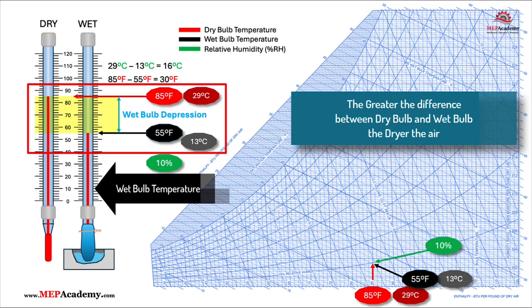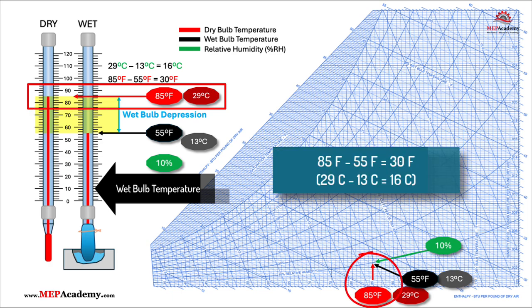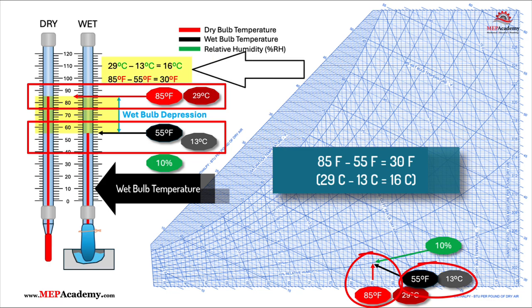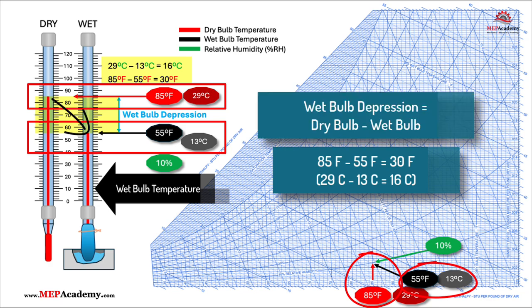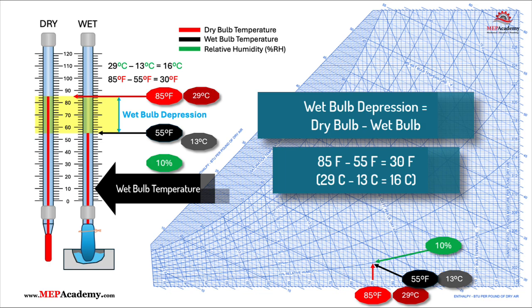We can see on this psychrometric chart that a dry bulb temperature of 85°F minus a wet bulb temperature of 55°F equals a wet bulb depression of 30°F, or 16°C. Wet bulb depression equals dry bulb temperature minus wet bulb temperature. A high wet bulb depression means there is significant potential for evaporative cooling.